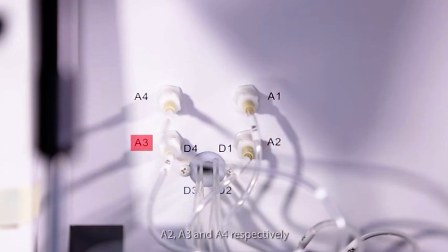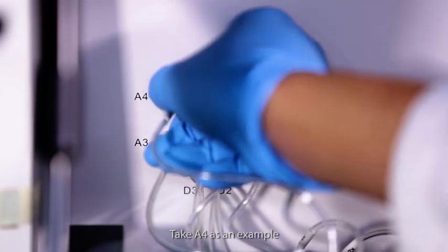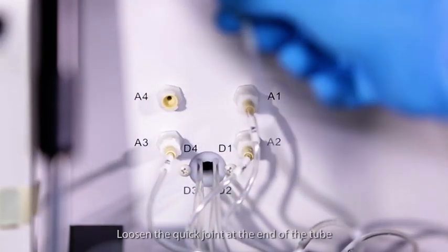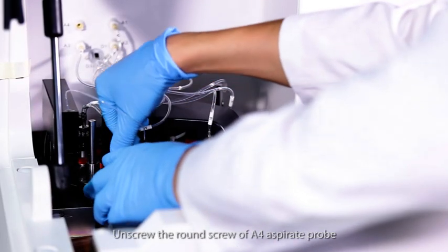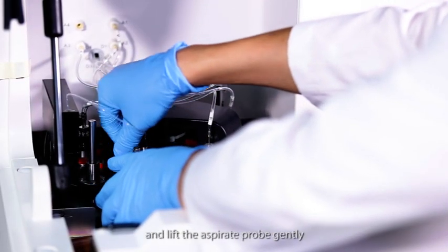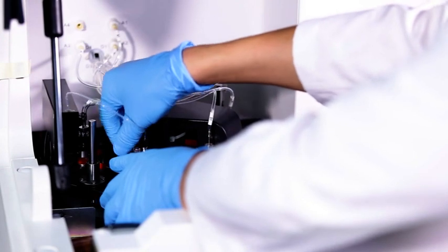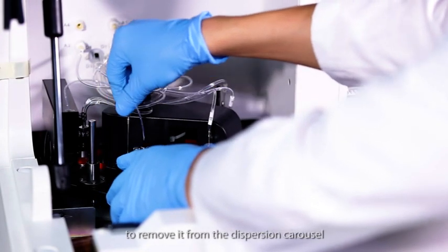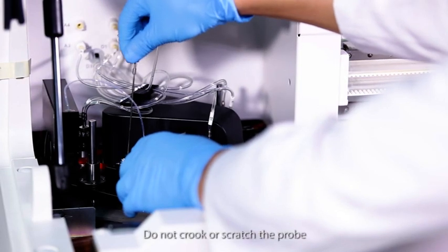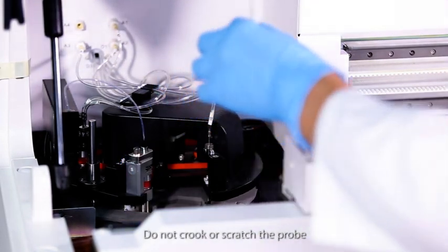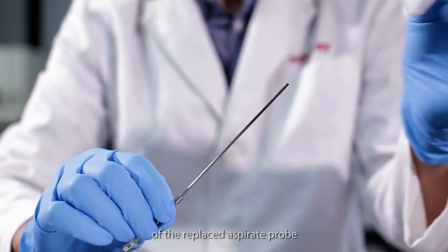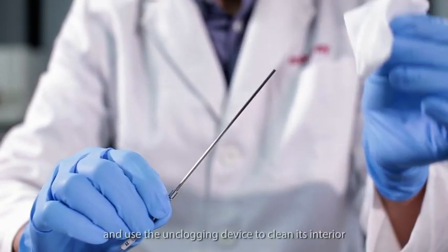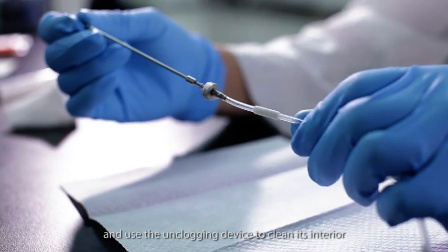The four dispersion aspirate probes are marked A1, A2, A3 and A4 respectively. Take A4 as an example. Loosen the quick joint at the end of the tube. Unscrew the round screw of A4 aspirate probe and lift the aspirate probe gently to remove it from the dispersion carousel. Do not crook or scratch the probe. Use alcohol swab to clean the exterior of the replaced aspirate probe and use the unclogging device to clean its interior.